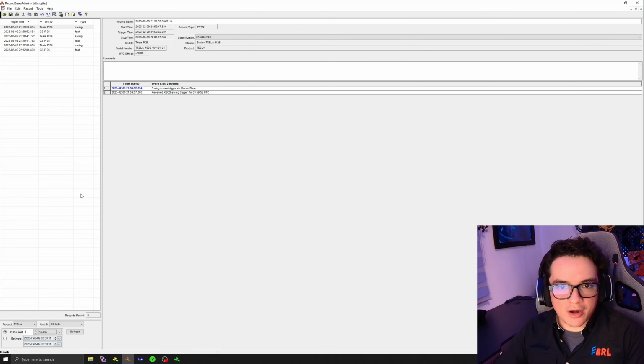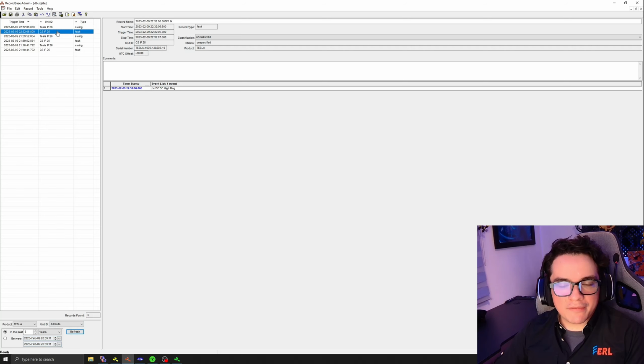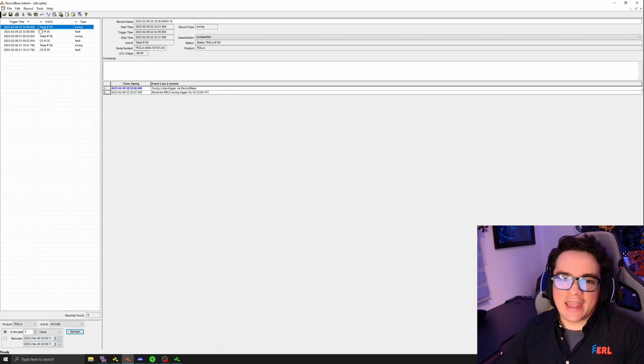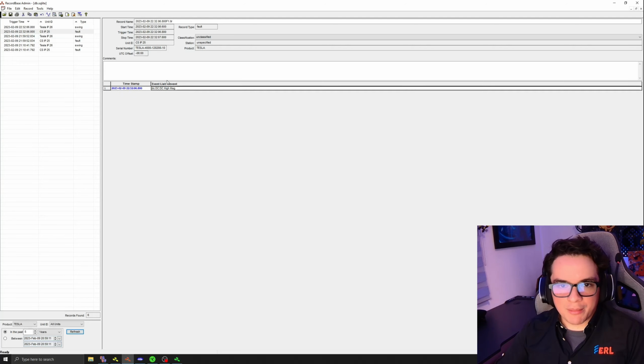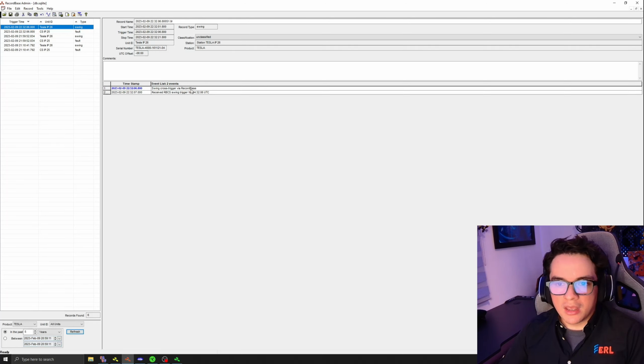Now let's go into our RecordBase system, RecordBase Administrator. All right, here we have the record that we created first, which was at 22:32:06 and 800 milliseconds. And now the other record on Tesla IP26 with the same stamp, thanks to both of them having an IRIG-B time sync. You can see here the DC high magnitude trigger, and then here in the event screen we have a swing cross trigger record via RBCS, and also received RBCS swing trigger for the UTC time.